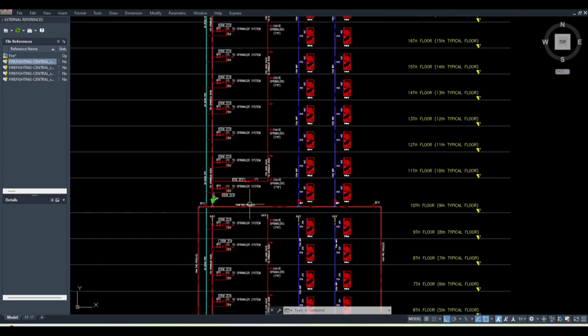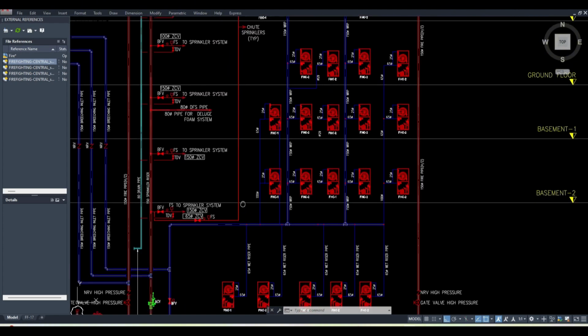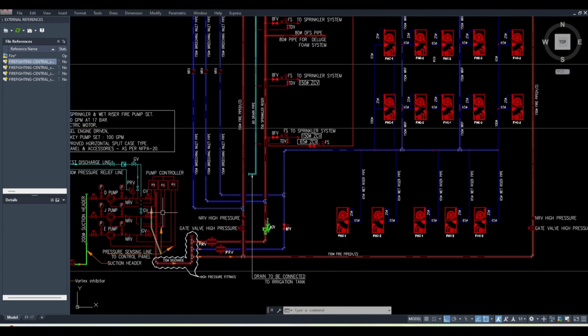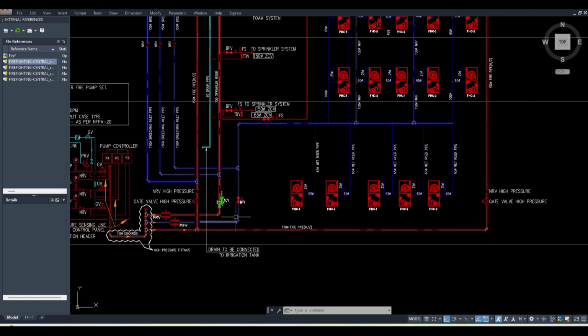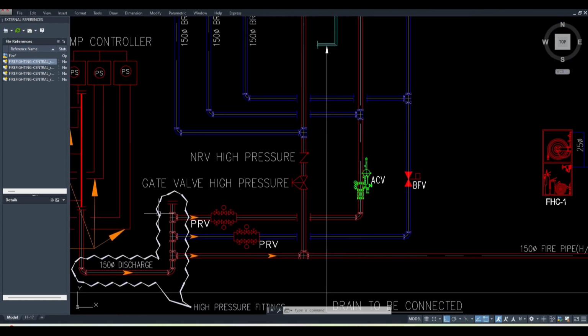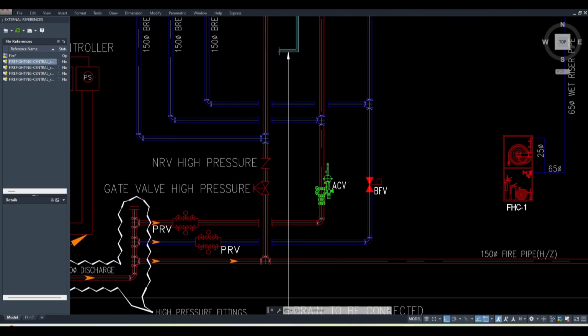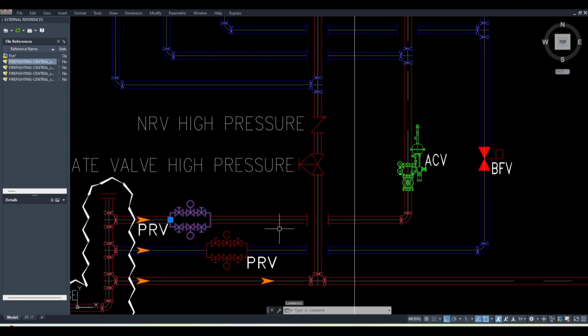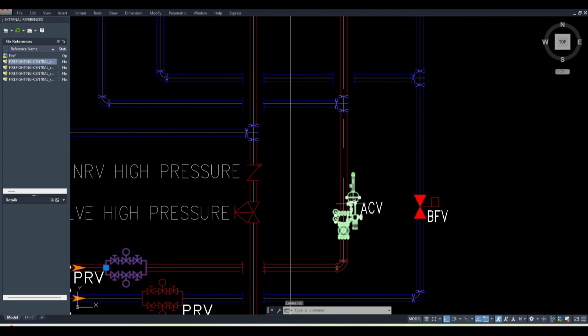Okay, so in the wet type, this was the color code. We are not going to deal with the dry type, we are going to use the wet type sprinkler. This system is combined with one pump room from where the pressurized water is coming. Then one line from that same pumping station comes out, and there is a PRV station, and then it goes to the alarm check valve, and then it goes to the sprinkler system.